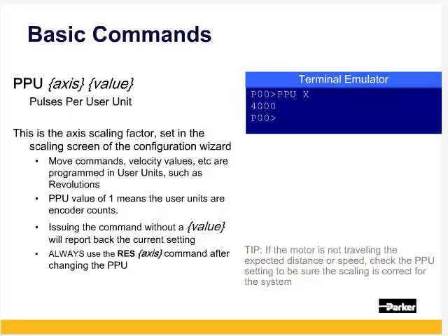Always use the res command after changing the PPU. If the motor is not traveling the expected distance or speed, check the PPU setting to be sure the scaling is correct for the system.